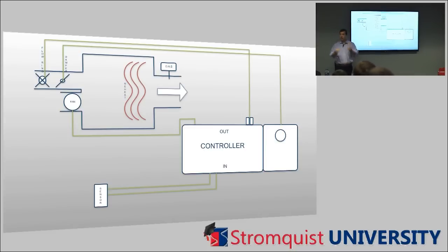Space temp and set point, right? Because that's what it's trying to get. So it says, I want my set point to be 70 degrees. And so then it's also measuring space temp. So when I get to 71 or 72 degrees, it's going to start the program that it's programmed to do and bring it back, opening the damper, turning on the fan, whatever we've programmed it to do when it gets above or below set point. All right, good.